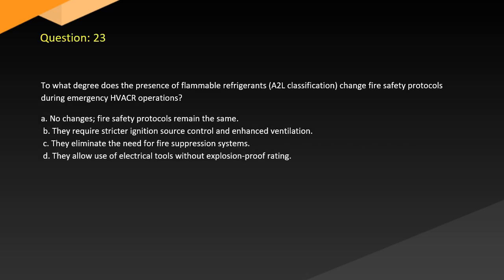Question 23. To what degree does the presence of flammable refrigerants, A2L classification, change fire safety protocols during emergency HVACR operations? A. No changes if fire safety protocols remain the same. B. They require stricter ignition source control and enhanced ventilation. C. They eliminate the need for fire suppression systems. D. They allow use of electrical tools without explosion-proof rating.